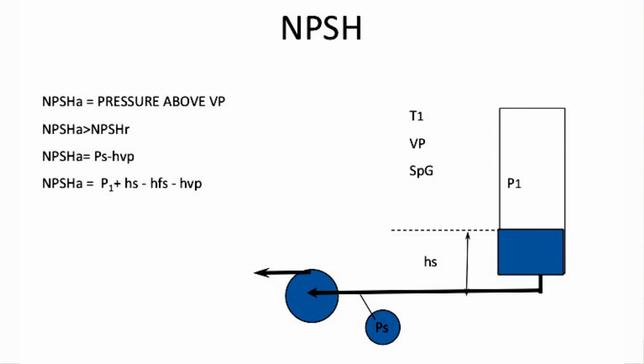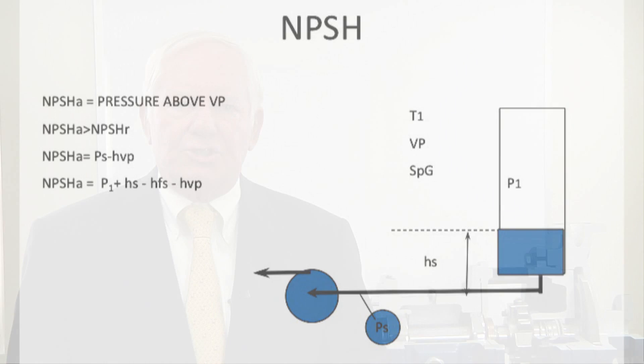For a new system being designed, you have to calculate it. You take the pressure in your suction vessel, add the static height of the liquid — or subtract it in the case of a lift — subtract the friction loss on the suction side, and then subtract the vapor pressure. Simple.